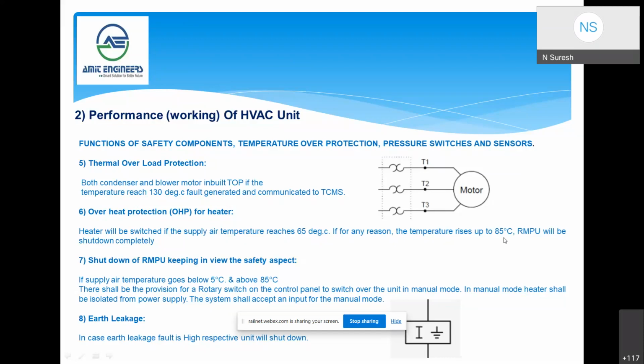There is also the supply air temperature sensor limit, programmed in such a way that if the temperature reaches 85 degrees, it will immediately give an indication and switch off. In case of any failure of the 65 level, there is the second level at 85 and the third level at 130 degrees, which is a fusible type.